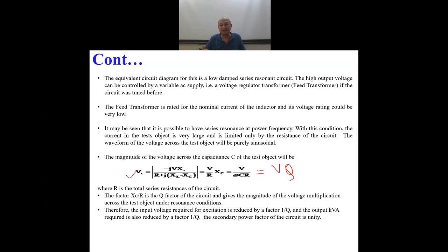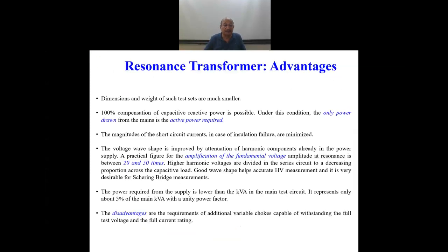If you had not compensated, you would have needed to apply much higher voltage to the test transformer. So that is a very big advantage. And if we read another advantage, the power required from the supply is lower than the KVA. Here, as you can see, last but one point, the power required from the supply is lower than the KVA in the main test circuit, because the magnitude of voltage you need to apply is very, very small. It represents only about 5% of the main KVA with unity power factor.